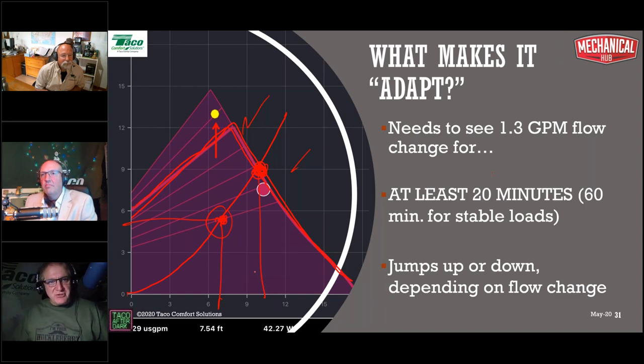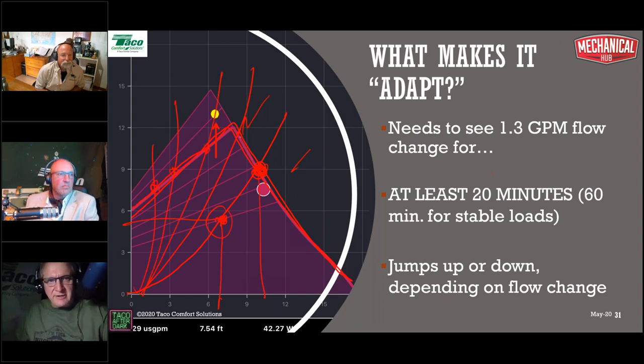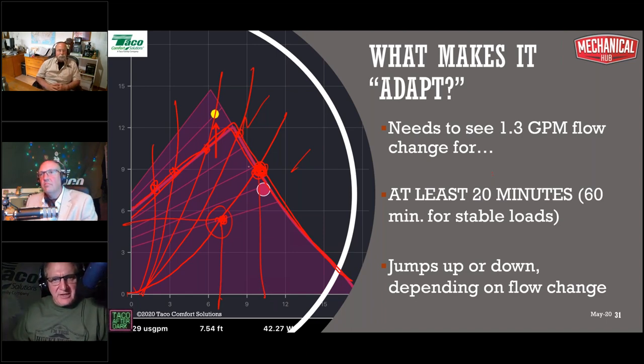And as zones close, this is what it's going to be doing. It's going to be working here and here and here and here and here. Now if this is an on-off system, guys, is it ever not going to work on that line? The answer would be no. It depends on how long the call is. If this thing's running for 90 minutes, it's got to run for 90 minutes to figure anything out. If we don't give it those 90 minutes to figure something out, it's never going to do anything different anyway. And that's in an on-off system, right?